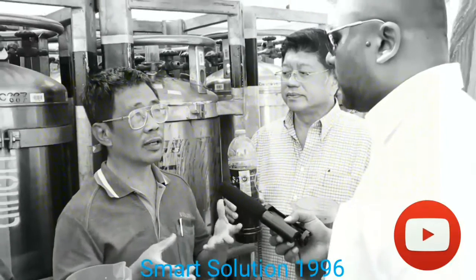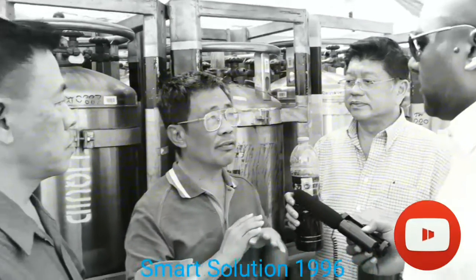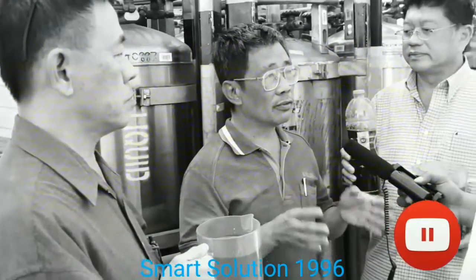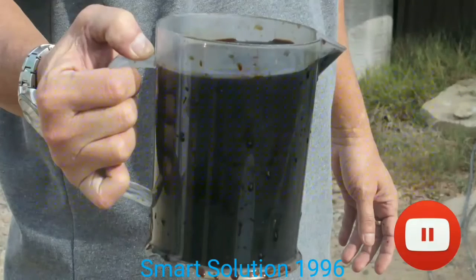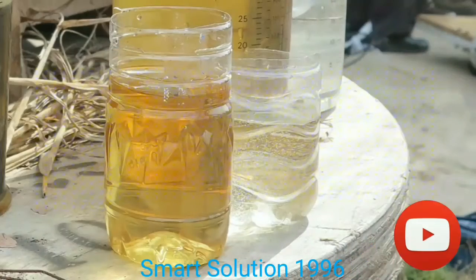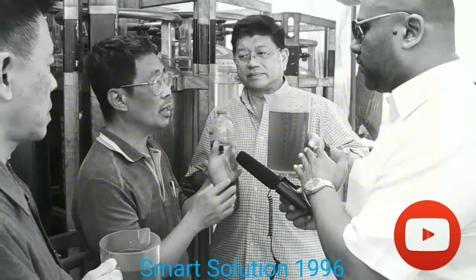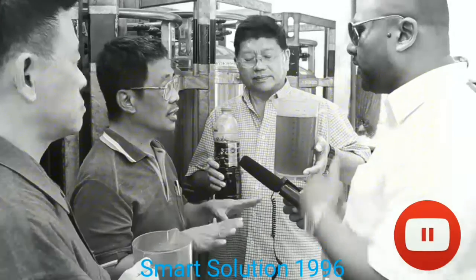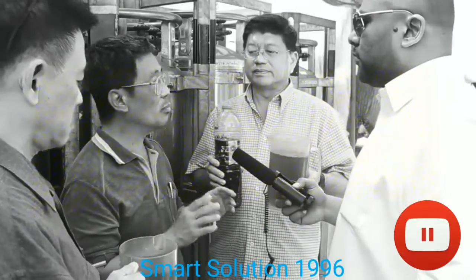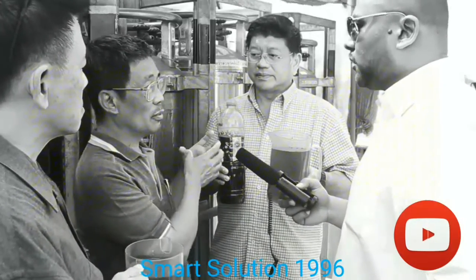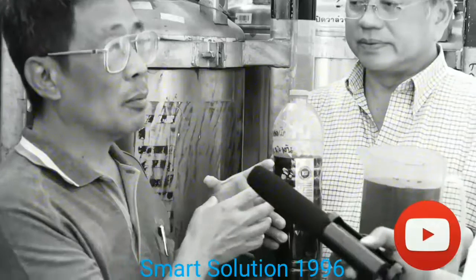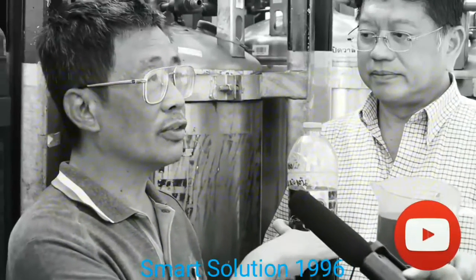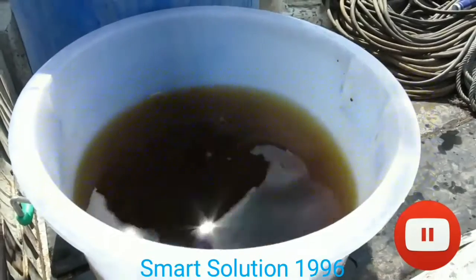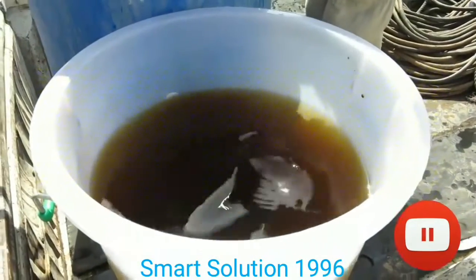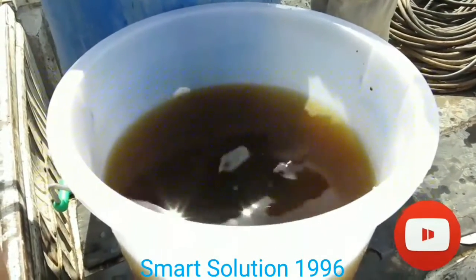Thanks to the technology, the process is very simple. When you get waste like this, you just dilute it to a manageable TDS value, which we should keep at no more than 500 in real production. The reason for 250 today is that we have a very small filter. If we put a lot of TDS in here, we get a lot of solids that the filter cannot absorb.